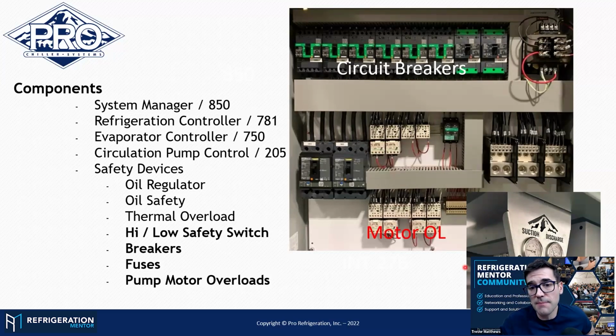I like that you bring that up. You got to make sure they're set properly. You got to go look at the motor, what's correct, the service factor on there, and make sure that you match that up, because somebody could go and start playing around with that. And this is why it's tripping, or it's actually tripping for a high load situation where you are overamping for certain reasons. And this comes back to you troubleshooting that system and understanding it. So don't just go and reset stuff before you understand the plan of attack. This is what I talk about in all my programs.